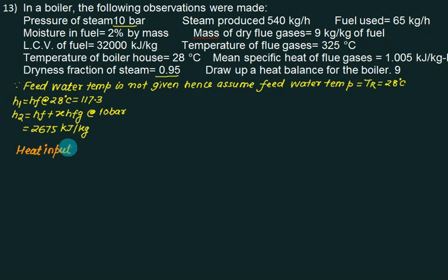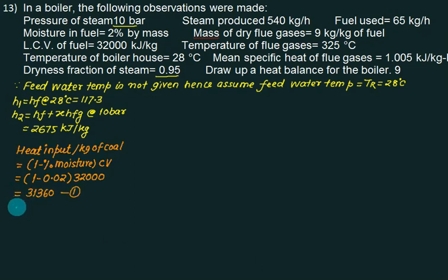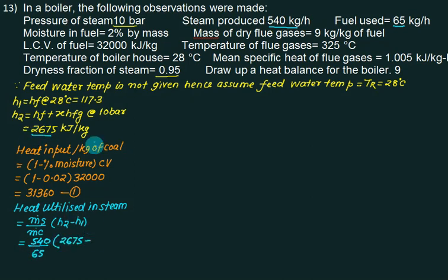Heat input per kg of coal equals 1 minus percentage of moisture. There is no ash but moisture is present, so this is 1 minus 0.02 multiplied by calorific value 32,000, which gives 31,360 kJ/kg of coal. Next, heat utilized in steam: our calculation is based on coal, so mass of steam divided by mass of coal multiplied by h2 minus h1. Mass of steam is 540, mass of coal is 65, so 540 divided by 65 times (2675 minus 117.3) equals the heat utilized.